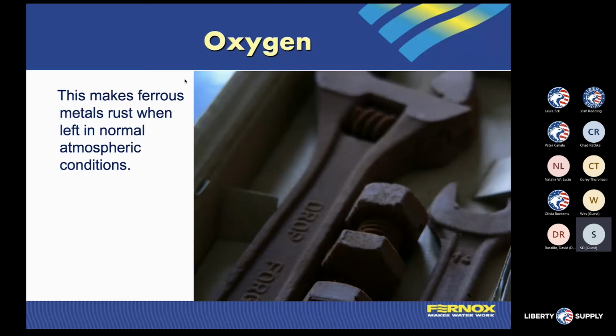But obviously, there is always a level of oxygen inside of that system, or if we're in a non-pressurized application, we would always have the readmittance of oxygen. Or if we're doing a non-oxygen barrier PEX tubing, that's another place where oxygen can intrude or come back into the system, to understand how that comes about.